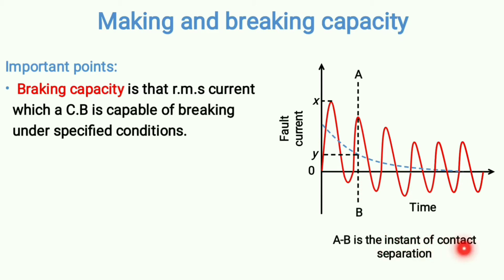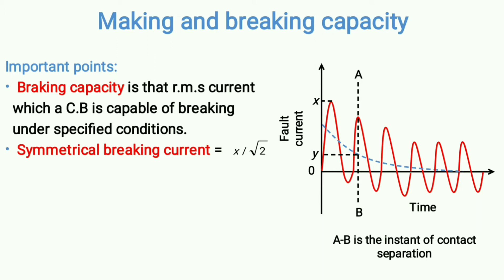AB is the instant of contact separation. Suppose the fault current has been sensed by the relay — the circuit breaker will try to separate the contacts. There are two types of breaking capacity. In the absence of the transient decaying component, the fault current becomes symmetrical. Symmetrical breaking current is X divided by root 2, where X is the maximum value — that is, the RMS value.